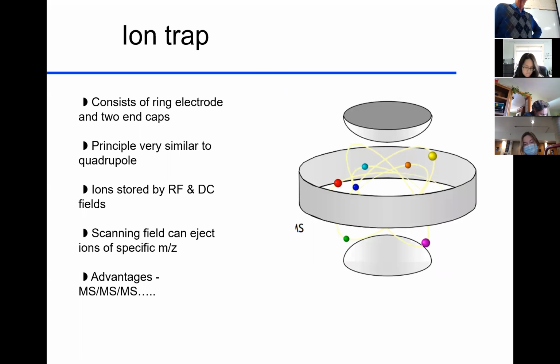The ion trap is just another way to separate these fragments. It's much more complicated mathematically, but it has the ability to take these charged fragments and collect them. So you can say, I want to collect a certain fragment, a certain mass. You can set it up so it collects that mass from the gas chromatograph and keeps on pooling it, and then releases it and measures it. In my other instruments, it's whatever's coming through that I get a response from. In this one, it keeps on collecting, and then releases so I can measure it.